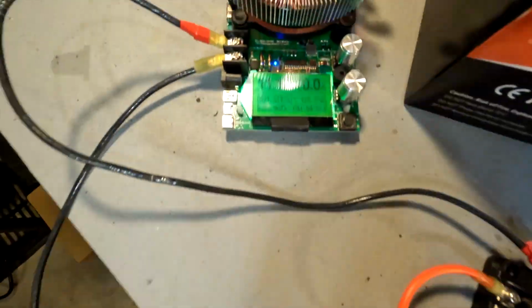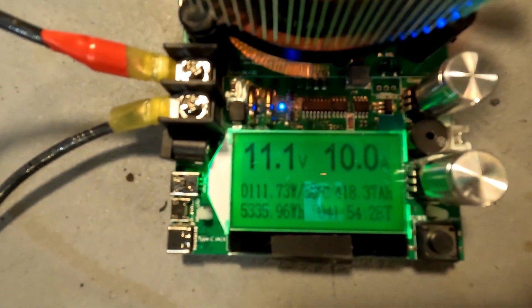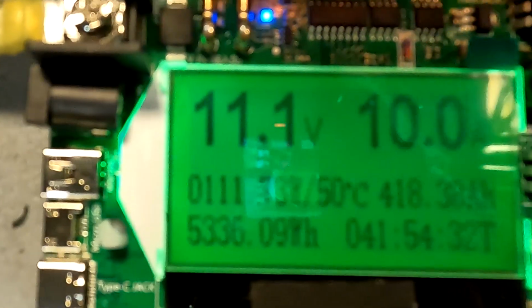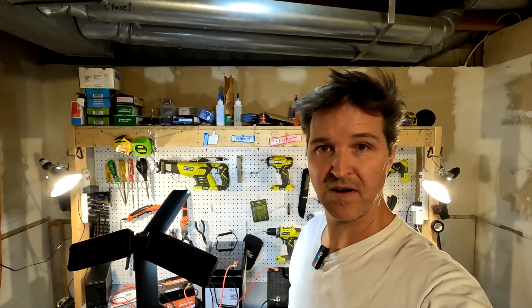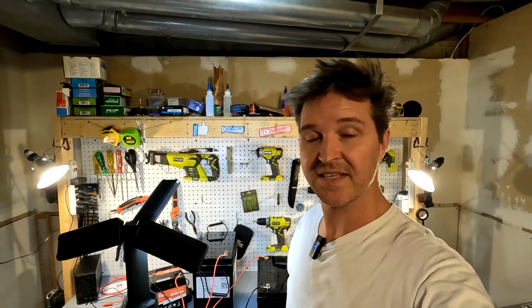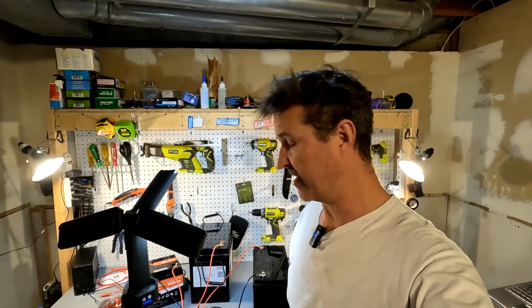Let's see what our tester shows. It shows 11 volts, still pulling 10 amps. We've pulled 418 amp hours from this bank, so that's pretty good. The time it took was 41 hours and 54 minutes. I truly think this bank could run for 42 consecutive hours before it completely depletes itself.